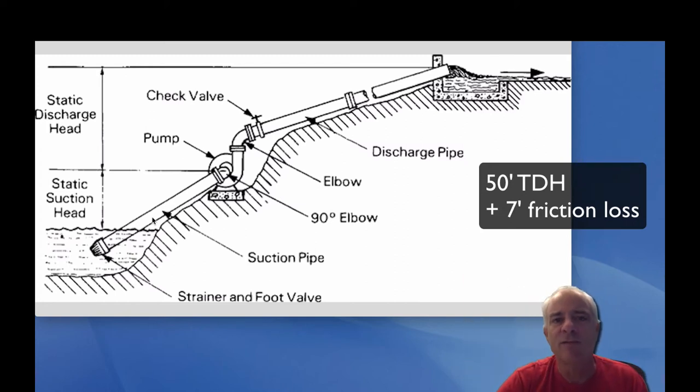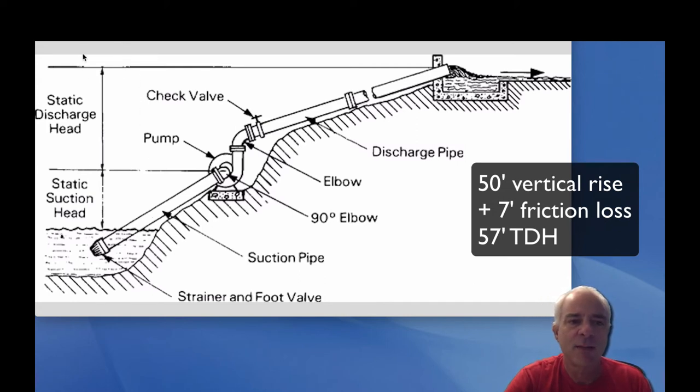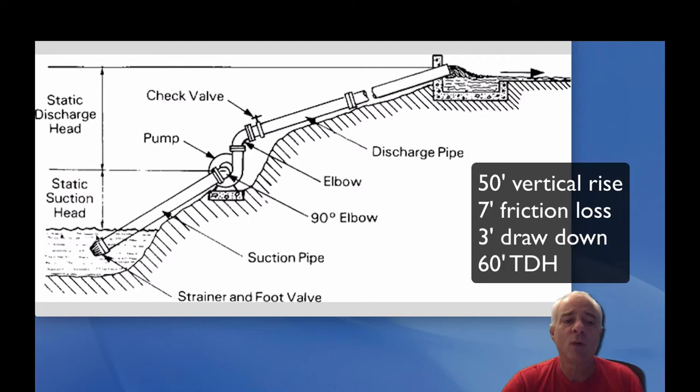So we have 57 feet now of total dynamic head. We also need to know while we're pumping, does this water level go down? This is very significant for submersible pumps in a well. Let's say we know this reservoir draws down about three feet. We want our pump to be able to pump when it gets down that low, so we add three more feet. Now we have 60 feet of total dynamic head.